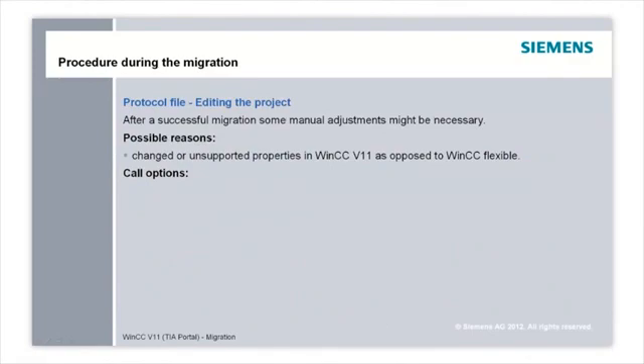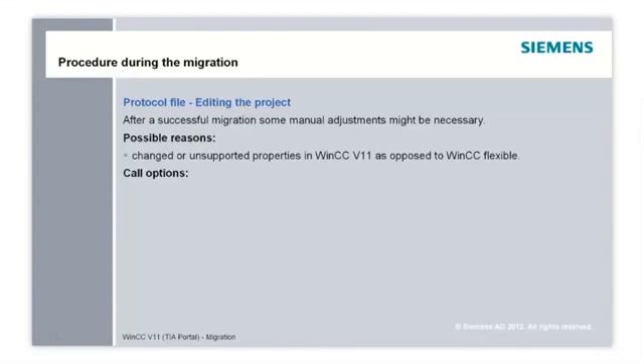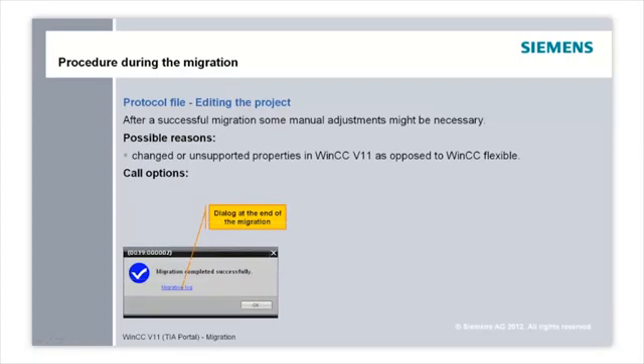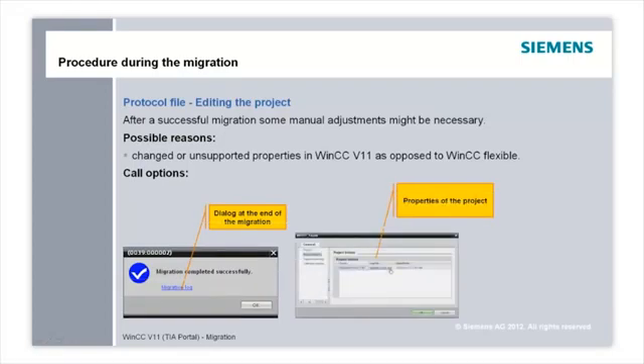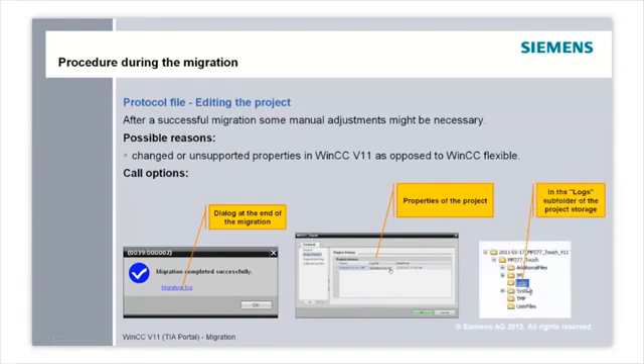After a successful migration, some manual adjustments might become necessary. Possible reasons include non-supported or changed objects, properties not realized in WinCC version 11 or realized differently than in WinCC Flexible, stricter criteria for checking tag addresses, or the length of object names in WinCC version 11. Object names in WinCC version 11, for example, need to be unique throughout the project — a picture name, even if located in a subfolder, can only be used once. Information on this is available in the migration log, which can be displayed via the dialog at the end of the migration, or via the properties of the project in the project directory in the logs subfolder.